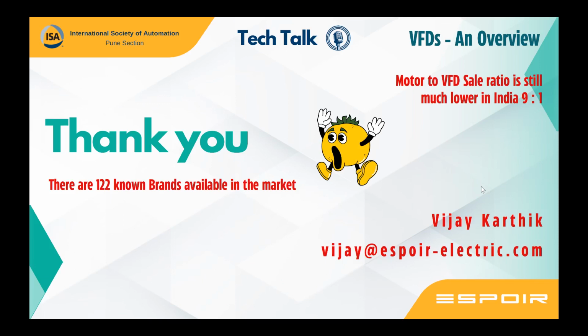In general, when there is a power failure, all systems shut down. But a pump in the HVAC industry should run if there is a fire incident. So the drive should have a feature where, if there is a fire incident, it should not trip, it should run continuously. So these are the three major aspects. Apart from that, it is purely driven by the consultant, and the consultant has a very specific brand, and only those drives go in.